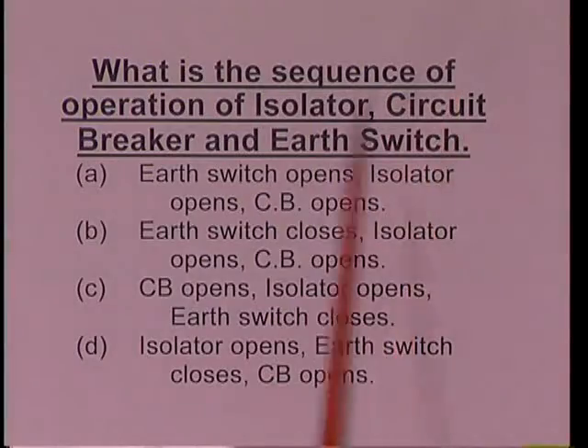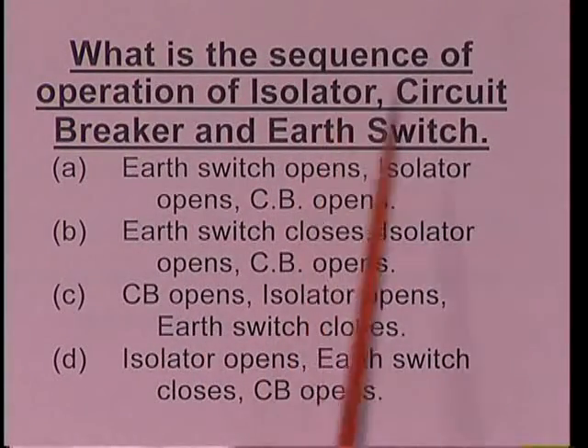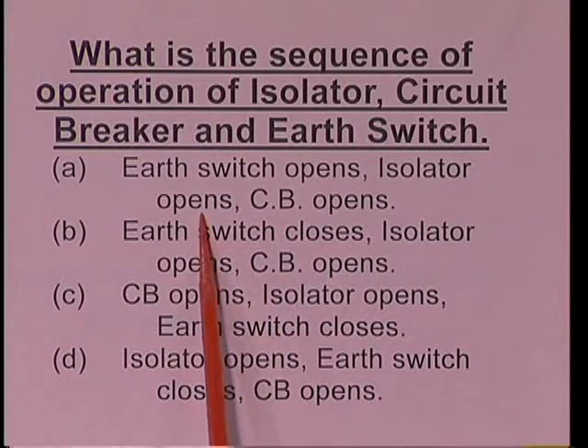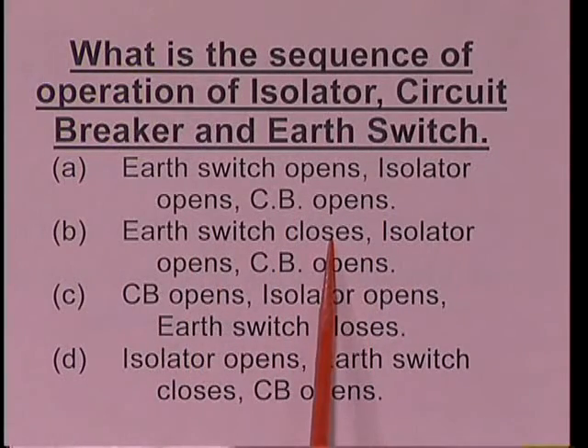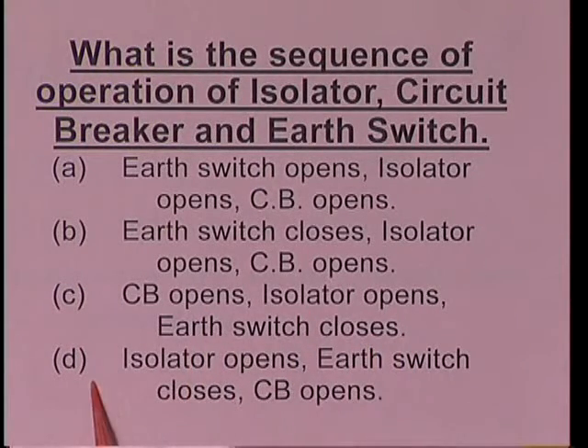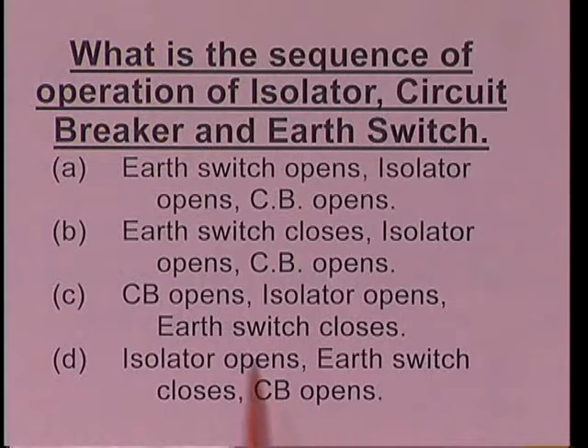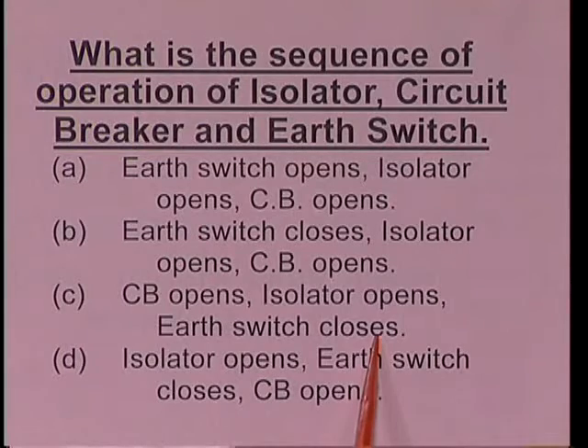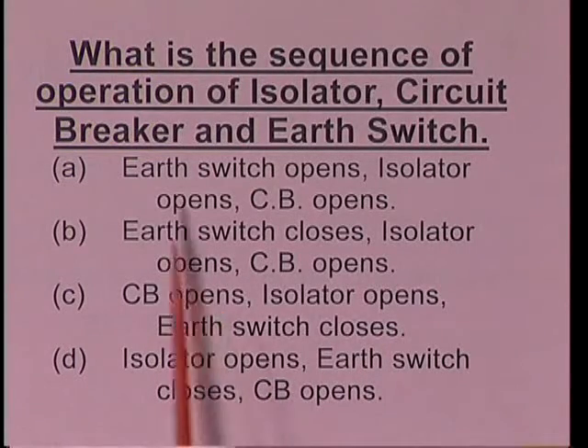What is the sequence of operation of isolator, circuit breaker, and earth switch? The correct answer is C: first circuit breaker opens, then isolator opens, then earth switch closes. The circuit breaker must be opened first because it is connected to the load, then the isolator is opened, and when the isolator opens the earth switch closes so that trapped voltages discharge to the ground.